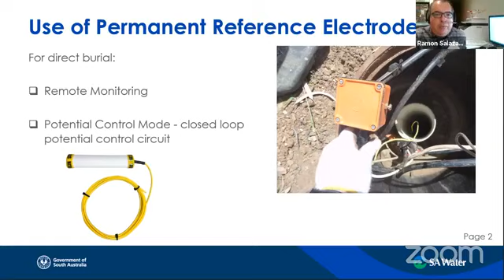Now, permanent reference electrodes are supposed to be permanent, but obviously they have a limited life, and there are some issues that can affect their life. One, for example, is the porosity of the porous plug. Contaminants can enter the reference cell, like chlorides in the case of copper sulfate reference electrodes. In the case of copper sulfate, copper ions can also leach out of the reference cell, and then the reference cell is not saturated anymore, and so you don't get correct readings.